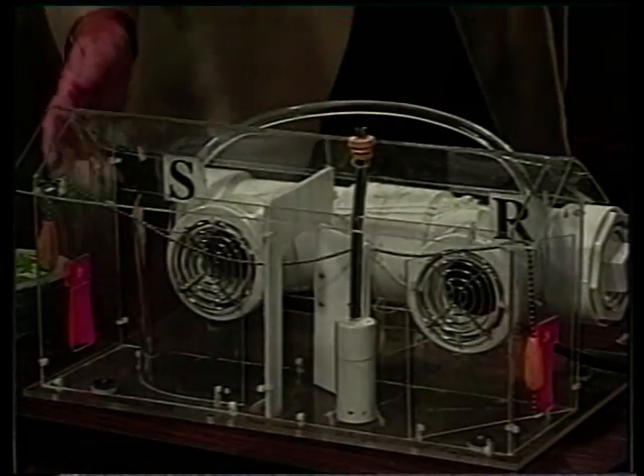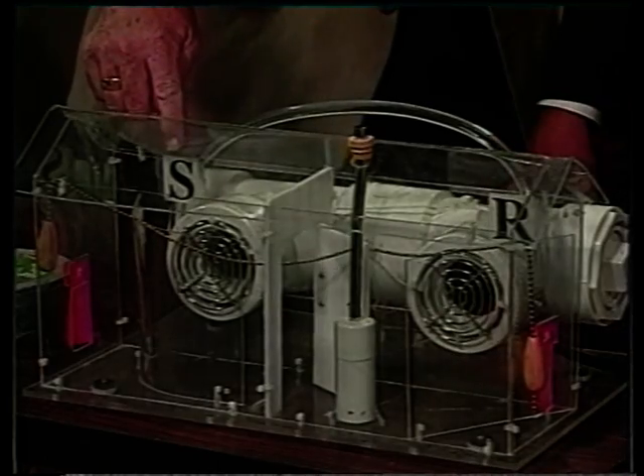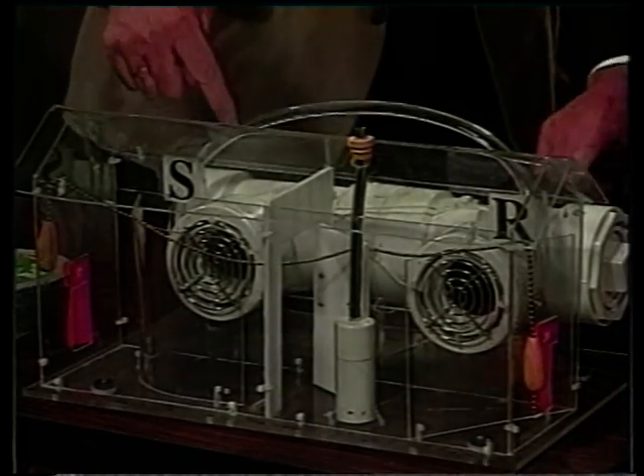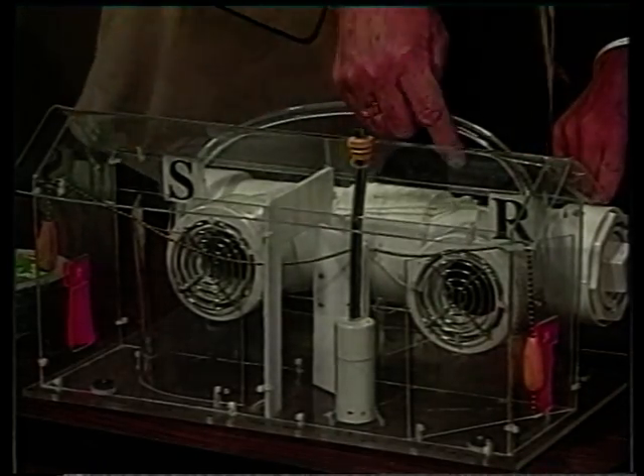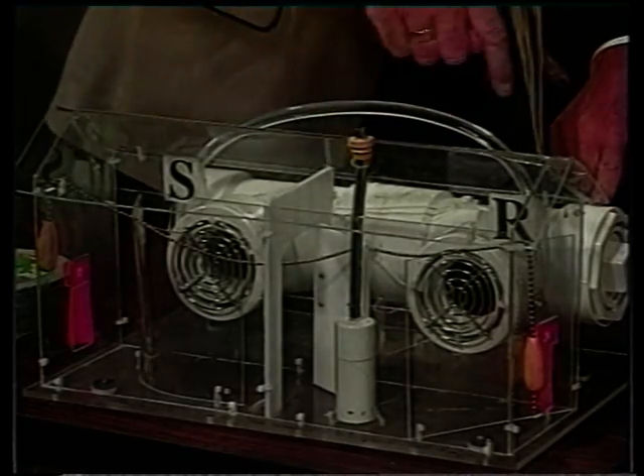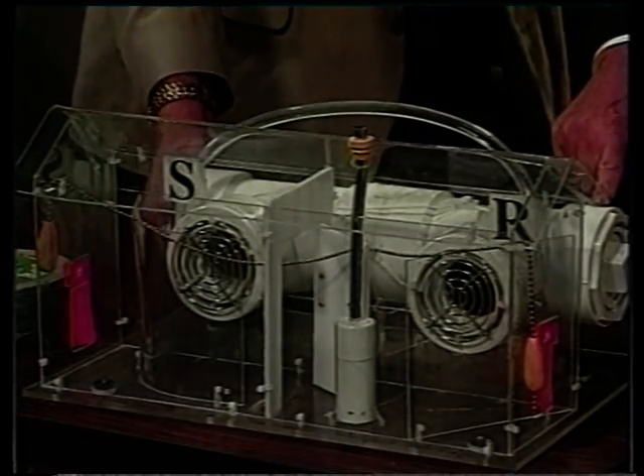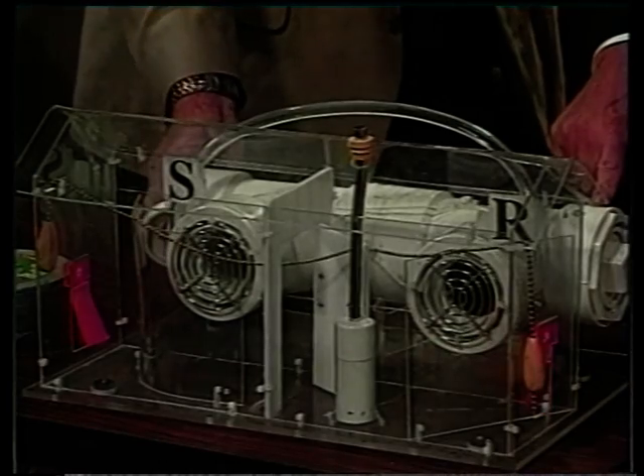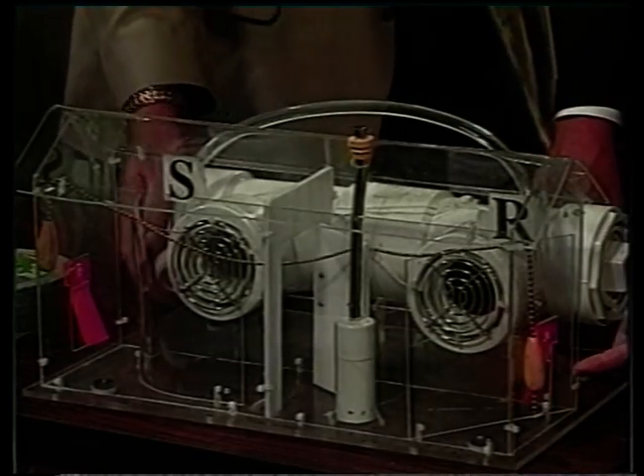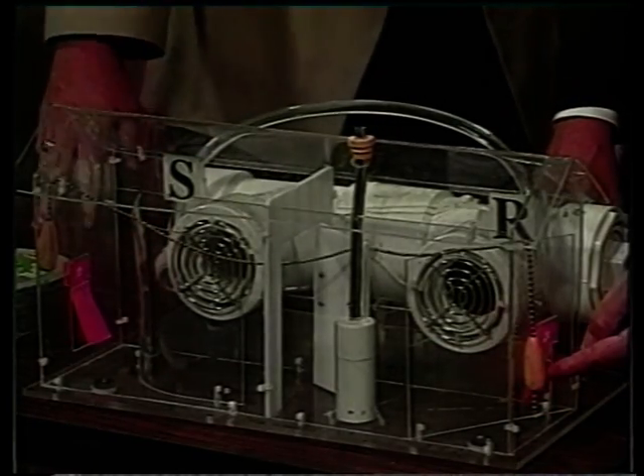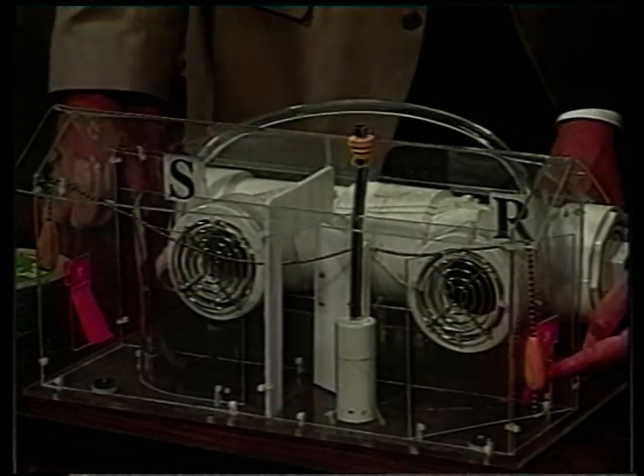Now watch my house. Here's the supply air coming into the house—here's the cooling coming in, and here's the return coming back to my unit. Watch what happens when I get leakage in the supply ductwork of my house. What did my doors do? They're going in, right? You can see there—my house just went big-time negative pressure.